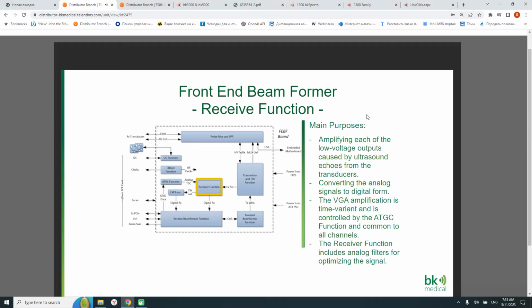The receiver function is amplifying each of the low-voltage outputs caused by the ultrasound echoes from the transducers and converting the analog signals to digital form. The amplification is time variant and is controlled by the ATGC function. This control is common to all channels. The receiver function includes analog filters for optimizing the signals in the frequency range of interest at the input of the AD converters. The receiver function receives its sampling and mixer clocks from the clock generator function.